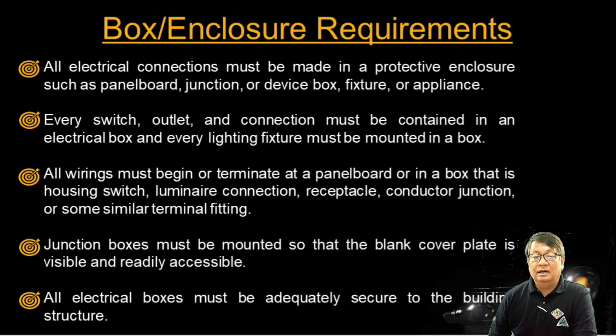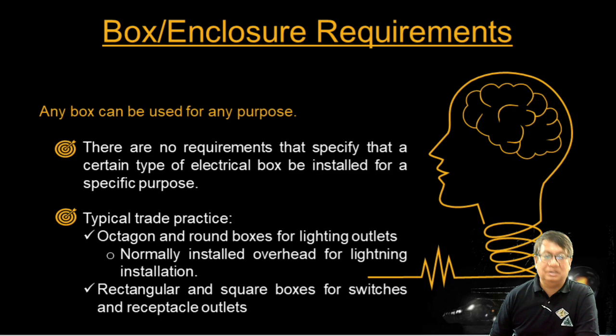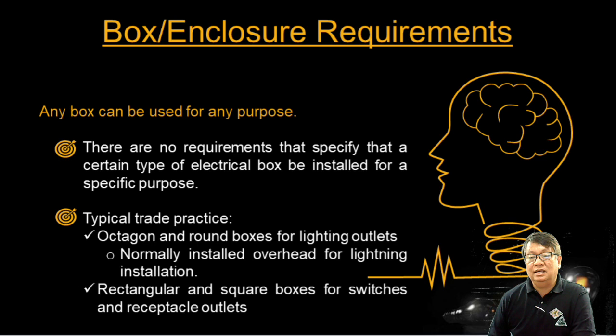Can any box be used for any purpose? First, there are no equipment requirements that specify that a certain type of electrical box be installed for a specific purpose. Typical trade practice is octagon and round boxes for lighting outlets, normally installed overhead, and rectangular and square boxes for switches and receptacle outlets.